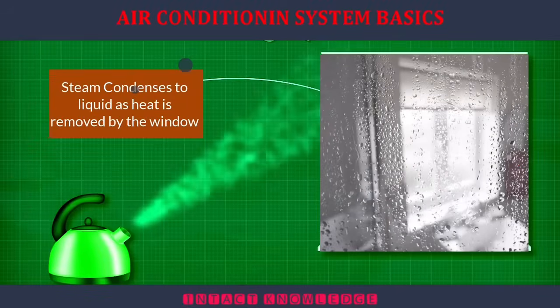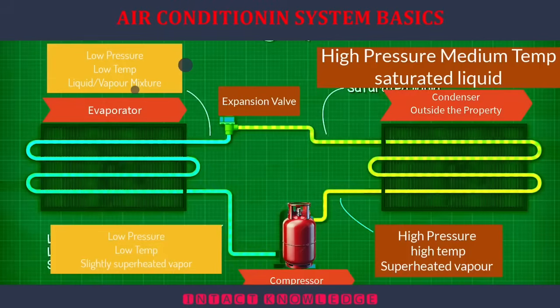It's a little bit like when steam hits the window on a cold day. The window is cold, so it condenses the steam from a vapor into a liquid, and then this liquid starts to run down the window. The refrigerant therefore exits as a high-pressure, medium-temperature, saturated liquid, and this heads to the expansion valve.